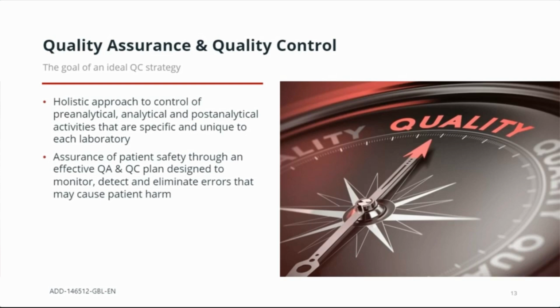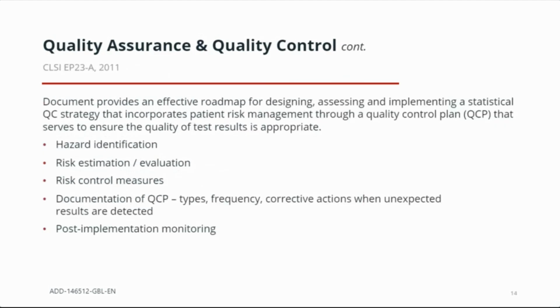So when it comes to defining QC frequency with patient risk in mind, where do we start? CLSI EP23 is another publication that provides an effective roadmap for designing, assessing, and implementing a statistical QC strategy that incorporates patient risk management through a quality control plan that serves to ensure the quality of our test results is adequate. That plan includes hazard identification, risk estimation and evaluation, implementation of risk control measures, documentation of our QCP, that is types, frequency, and corrective actions when unexpected results are detected, and post-implementation monitoring. So this is a nice checklist of tools to consider, not all encompassing, as you can imagine, due to advances in technology, but it is a good starting point.